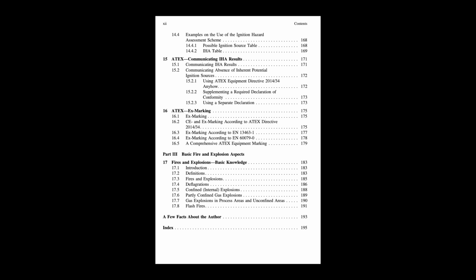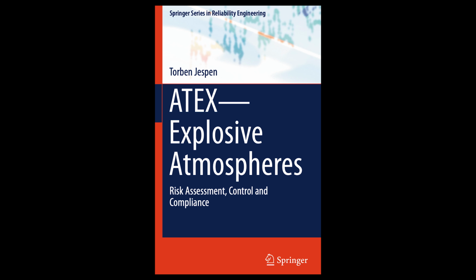Ex p is pressurization, which keeps the flammable atmosphere out with positive pressure, for various zones. Ex m is encapsulation, which seals components, for all zones. Ex n is a category for Zone 2 only, less stringent than others. And for dust, Ex t signifies protection by enclosure, focusing on dust ingress prevention and surface temperature limits. So the code tells you how it's protected. Yes, and therefore which zones it's suitable for.